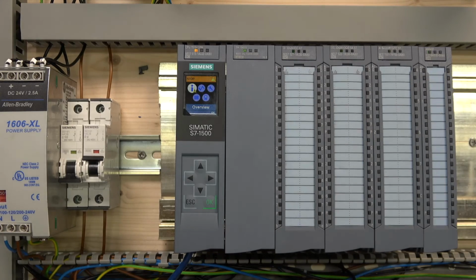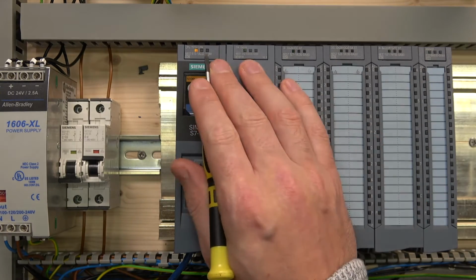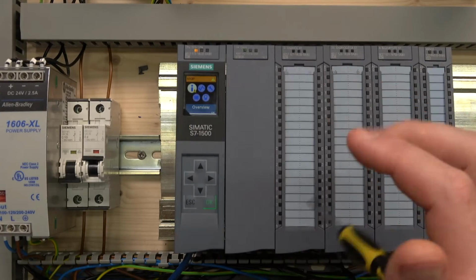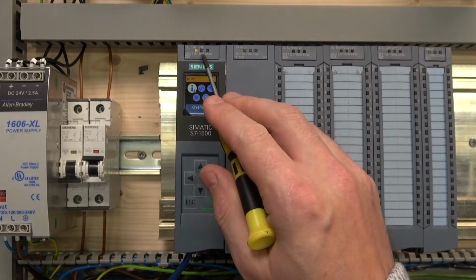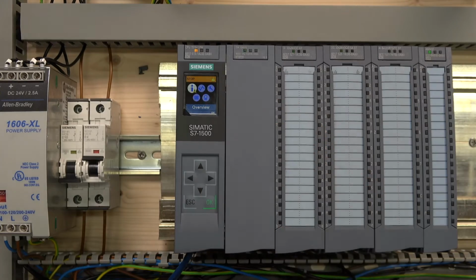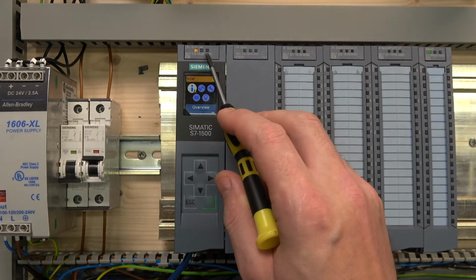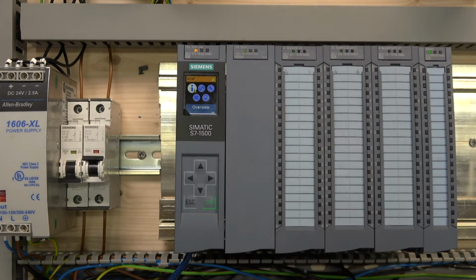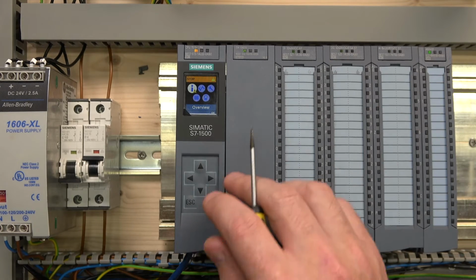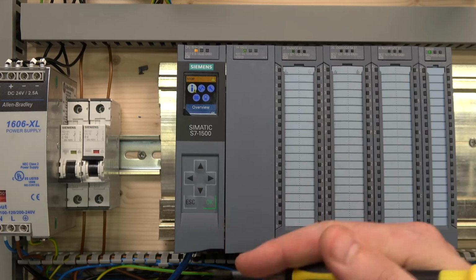So here we are. First thing, let's have a look at these status lights. For the CPU, you have a basic status light in here, which is the orange and green between start and stop. You have an error light, an old indication called SF, and this one in here is going to be your maintenance light. Later on, we're going to see if we can find ways of turning on maintenance. It's usually when you use the memory card or are updating or other things that the maintenance light will come on.